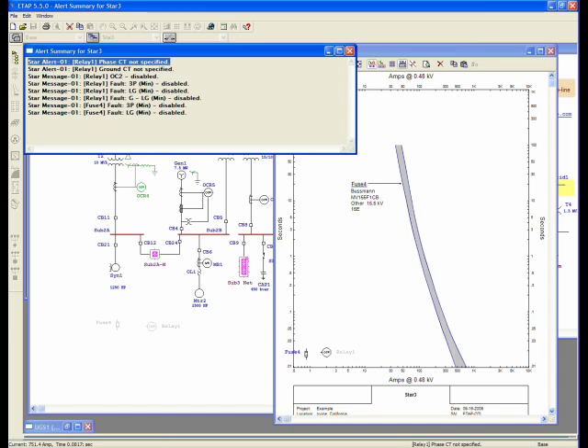One is star alert 01, which says relay 1, the phase CT is not specified. And it also says that the ground CT is not specified. The other message is just telling you that you've disabled default clipping values into star.